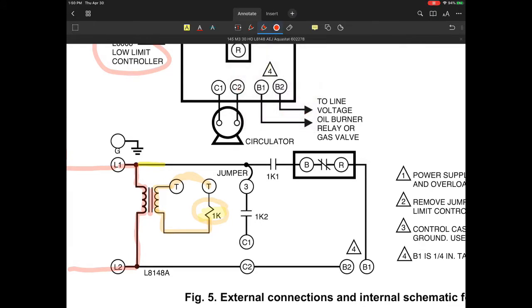And what's going to happen exactly when that goes on? Now, even before that relay gets energized, we're going to be feeding line voltage directly to the 1K set of contacts, which is going to be prior to the high limit. So this B and R is actually going to be, let me mark this out here, your high limit. So that's going to be the limiting device for your water temp. Whatever you set that to, it should not go above that.